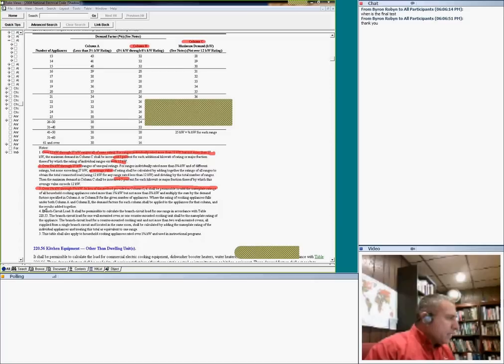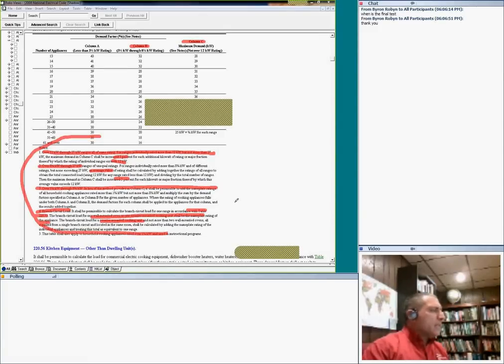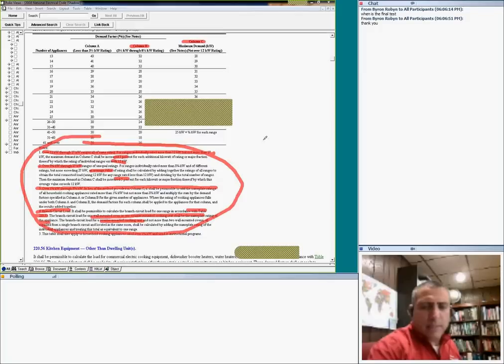Branch circuit loads: it's permissible to calculate the branch circuit for one range. According to this table, you can apply the branch circuit load for a wall-mounted oven, and so on. If it's two ovens and one cooktop, a counter-mounted cooking unit, you treat them as a range. All this, guys, is for residential only. Any questions, my friends, about these?